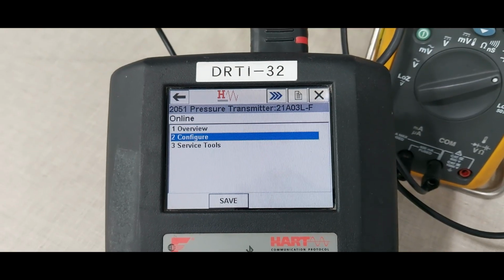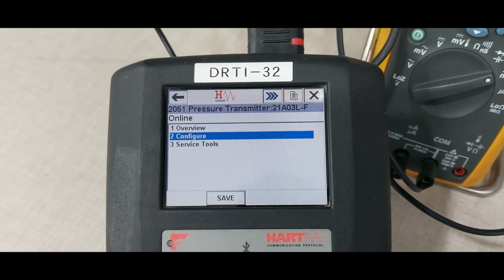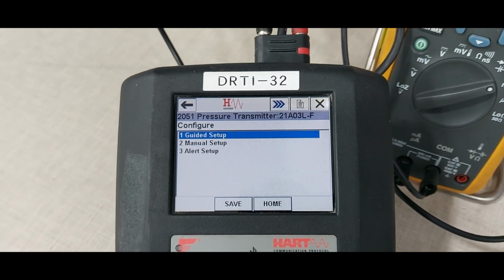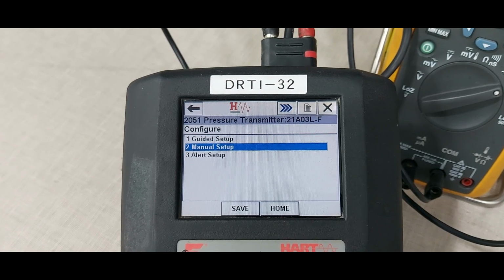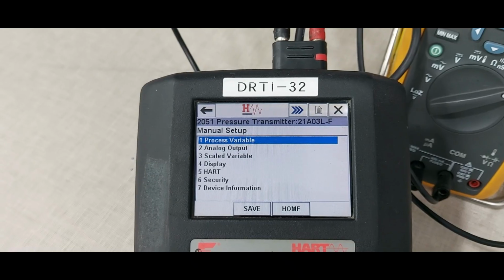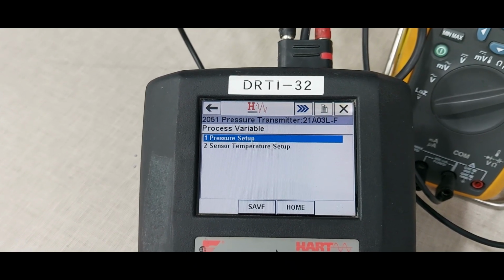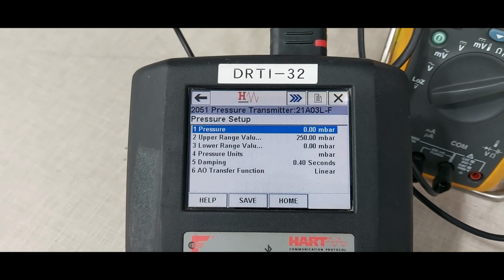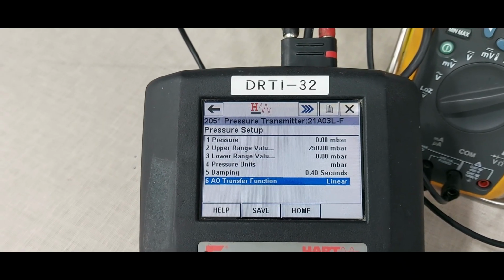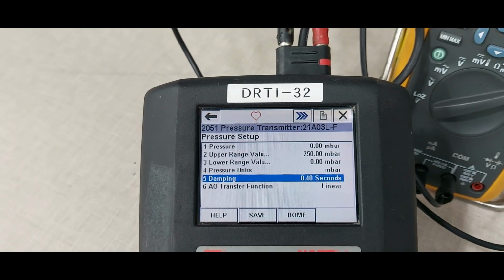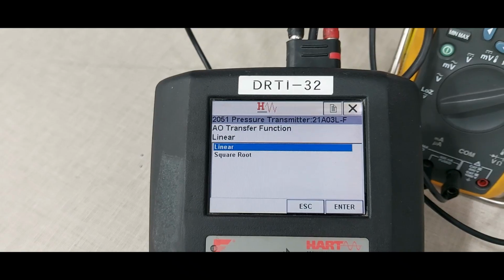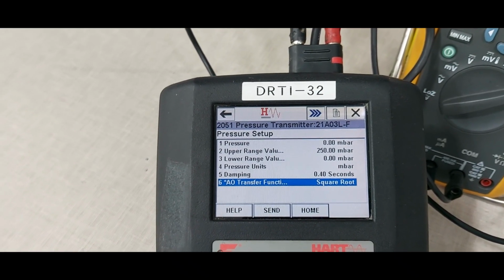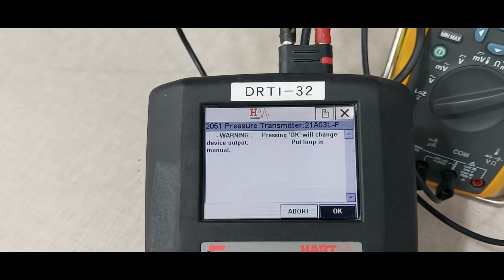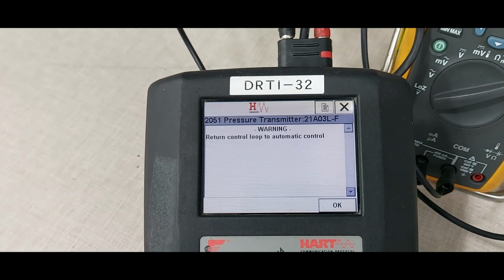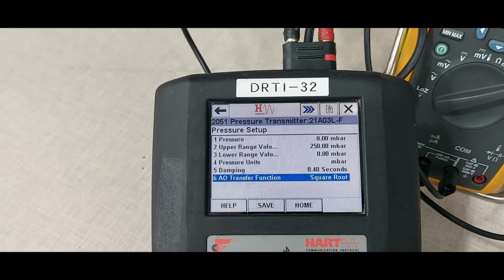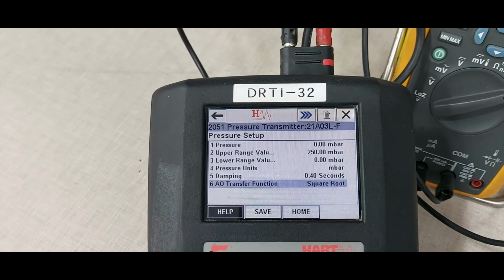Next we are doing the analog output transfer function configuration procedure. Select the configuration menu. Select the manual mode setup. Select the process variable. Select the pressure setup. And the sixth, analog output transfer function. Select it. Number 6. Select square root. Send it. Then OK. OK. Now analog output transfer function configuration is completed.